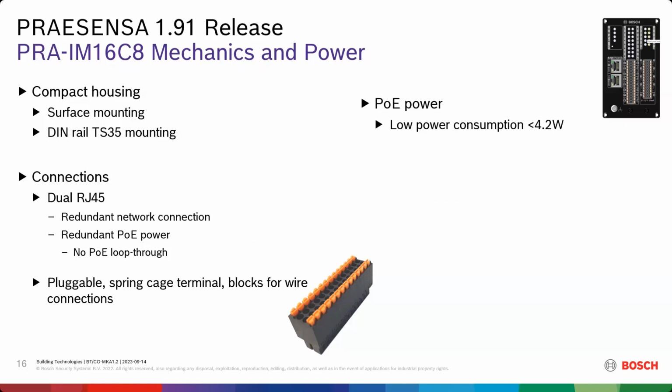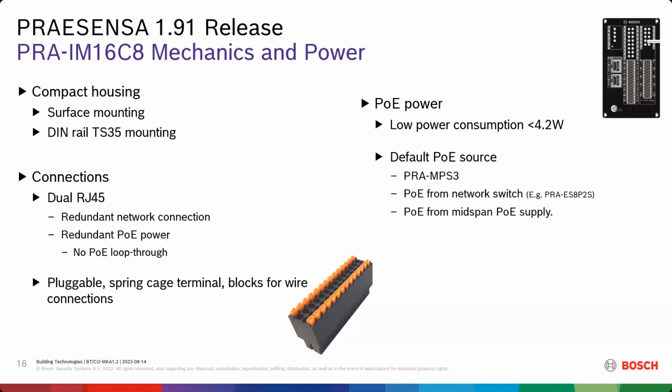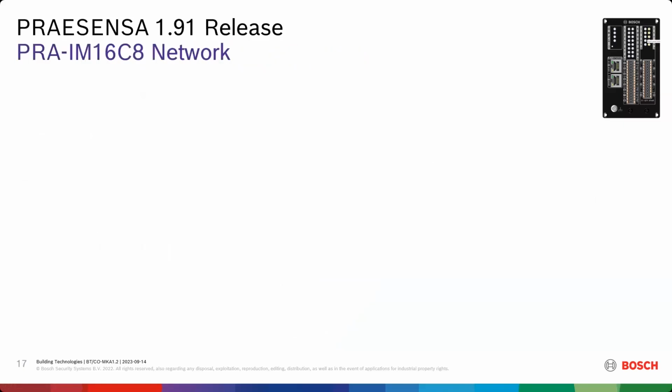The PoE power is less than 4.2 watts, and it's a default PoE source which you can use, like the MPS3, which has two PoE ports where you can directly connect this device, or from a network switch like the ES8P2S. Both of these, the MPS and the ES8P2S, are EN54 certified. You could also use a midspan injector for PoE supply, but then your connections to this device are no longer EN54. So maybe for other purposes you could still use it, but not for EVAC related aspects.